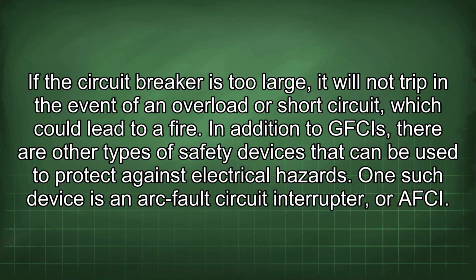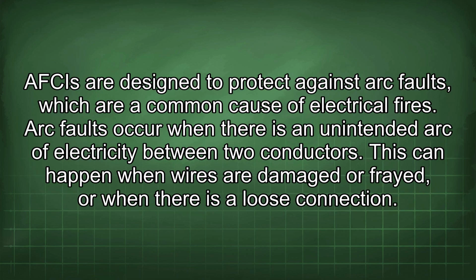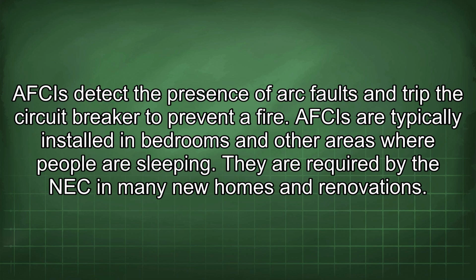In addition to GFCIs, there are other types of safety devices that can be used to protect against electrical hazards. One such device is an arc fault circuit interrupter, or AFCI. AFCIs are designed to protect against arc faults, which are a common cause of electrical fires. Arc faults occur when there is an unintended arc of electricity between two conductors. This can happen when wires are damaged or frayed, or when there is a loose connection. AFCIs detect the presence of arc faults and trip the circuit breaker to prevent a fire. AFCIs are typically installed in bedrooms and other areas where people are sleeping. They are required by the NEC in many new homes and renovations.